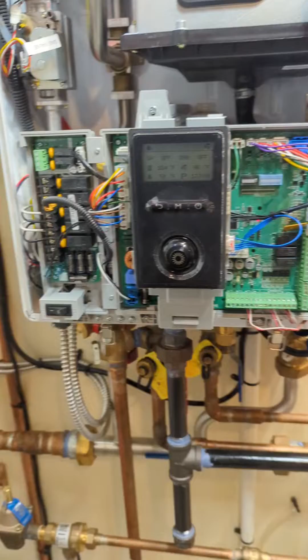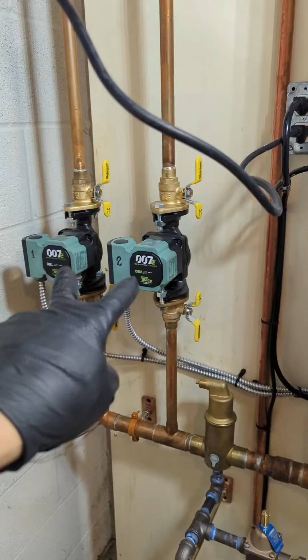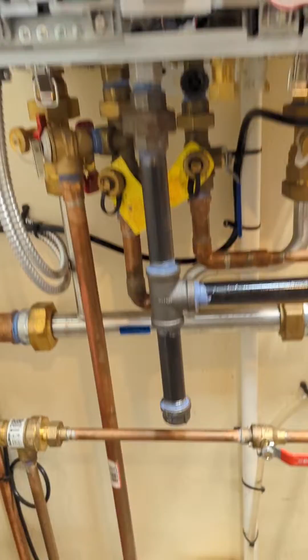The best and easy way to check is you turn on the heating side, which is your thermostat. They have two zones on this one. Turn off the thermostat so it's not calling for heat. This is the primary loop here for the heating side, that stainless steel primary loop, see? And this is the secondary.